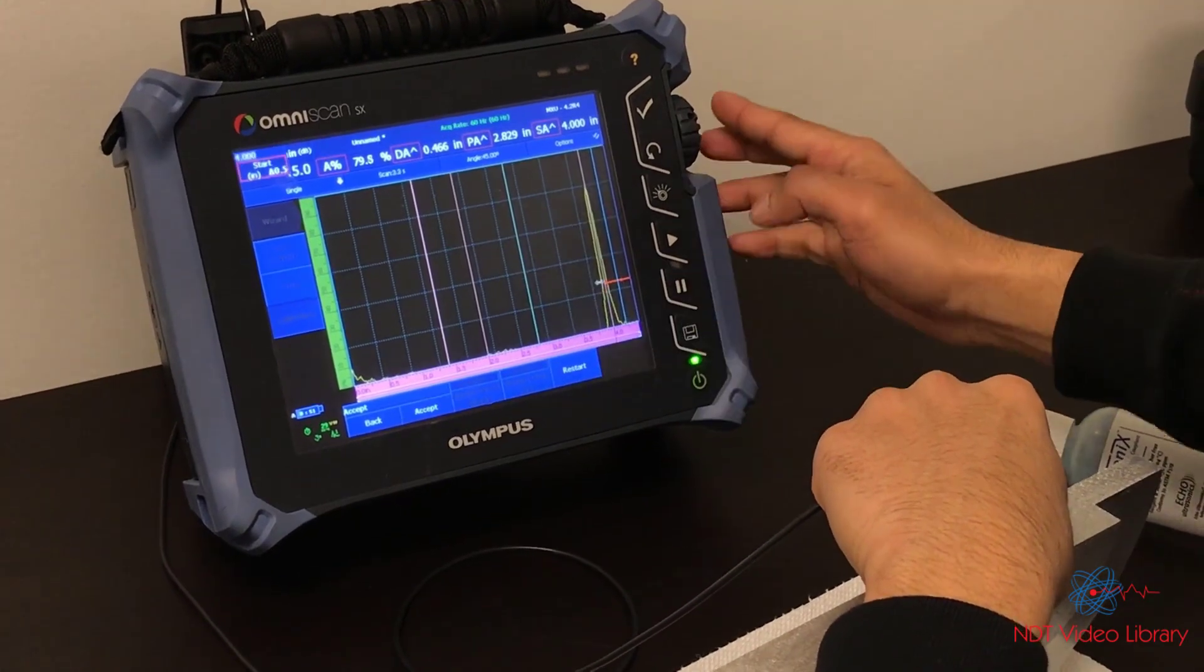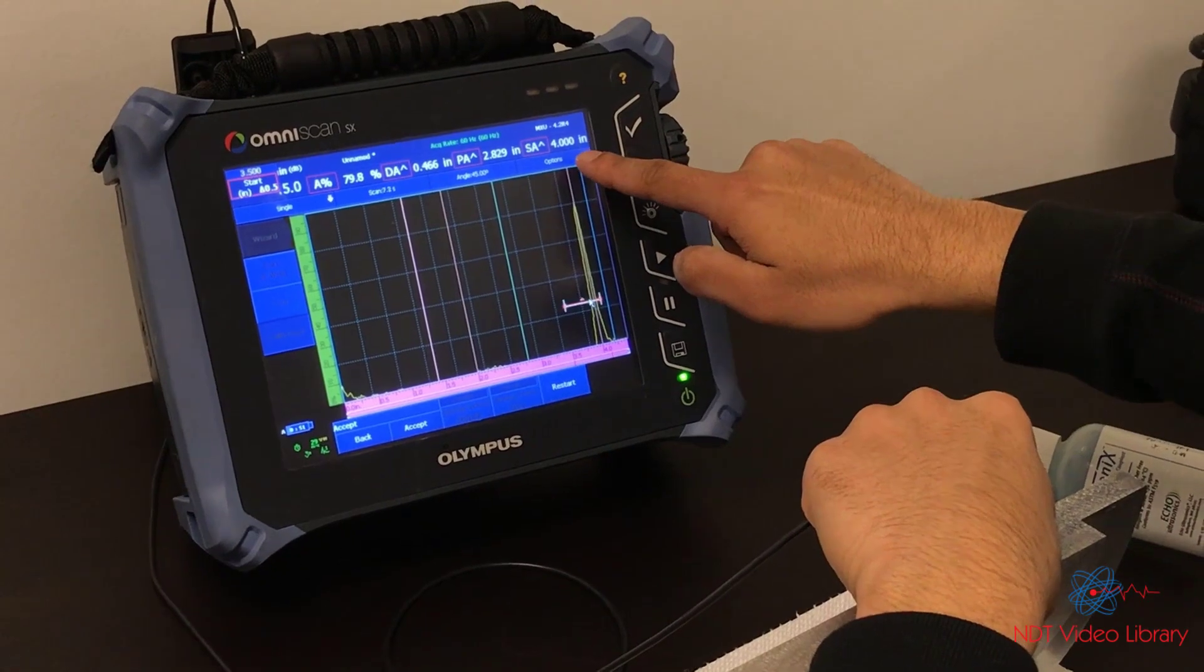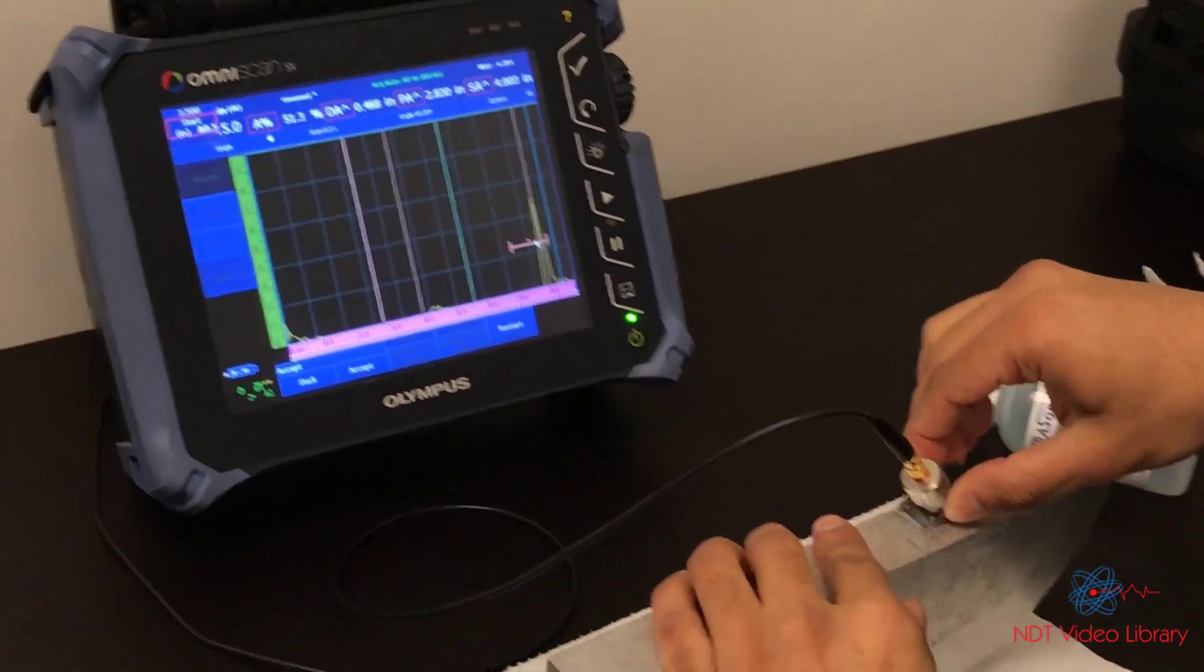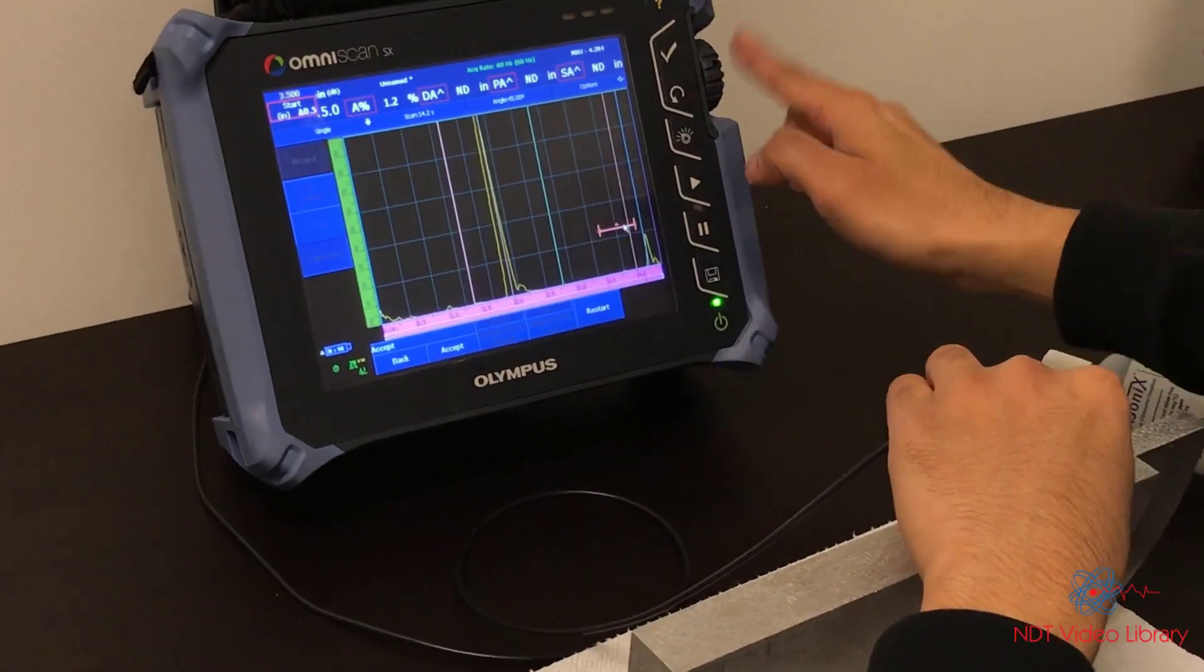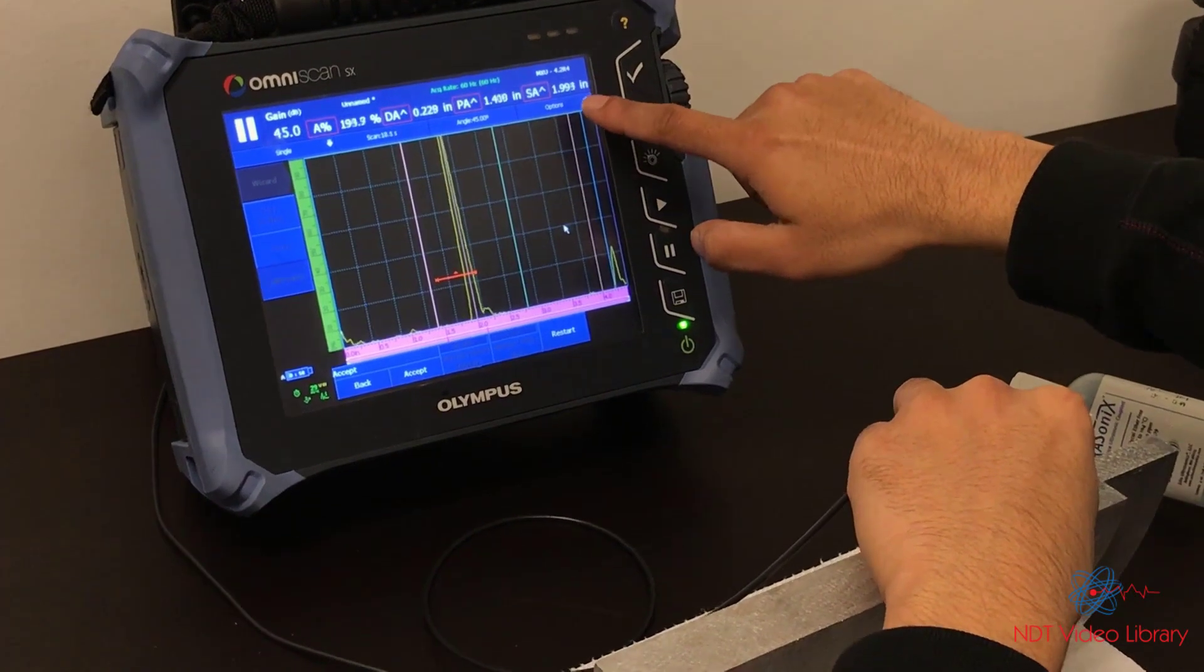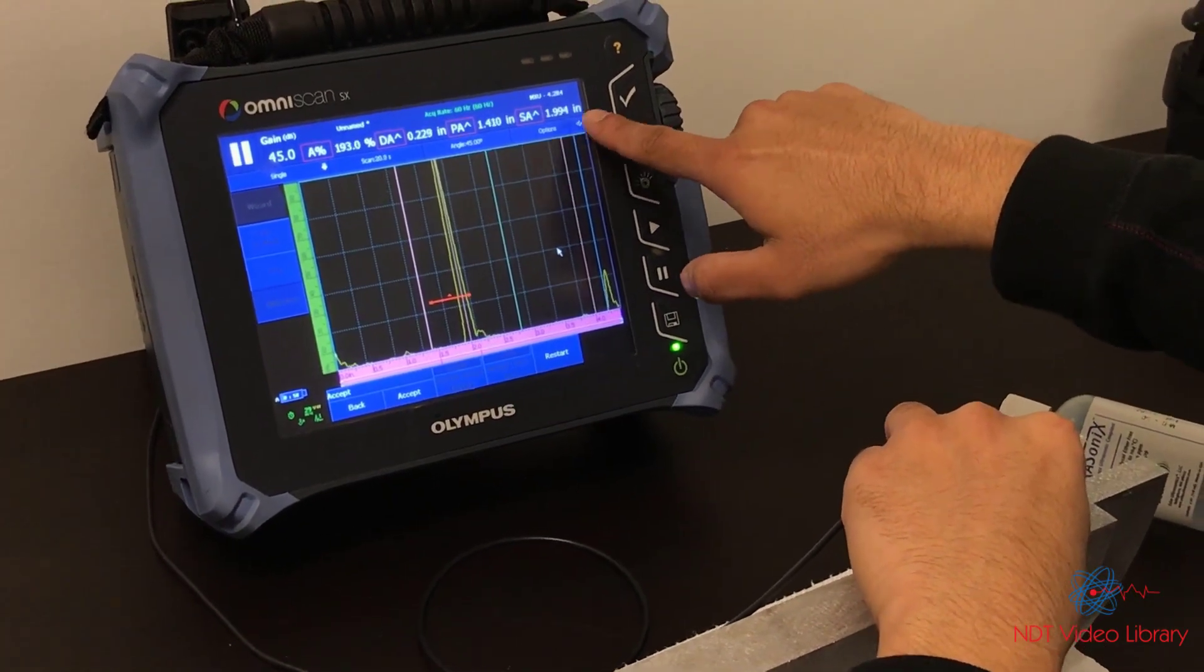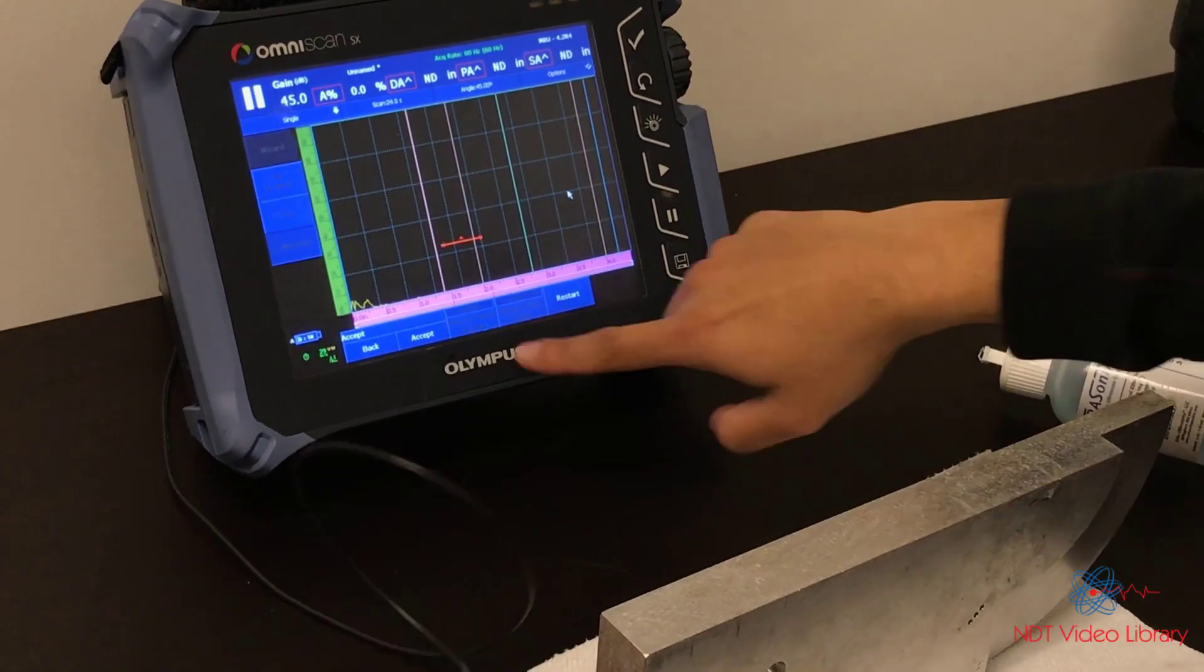Now you can verify if you want. The beam path here says 4. And if I want to check the other one, which was the 2 inch one, I'm going to move the gate over there. The beam path says almost 1.99, which is 2. So that means we calibrated it. And then we hit accept. That's it.